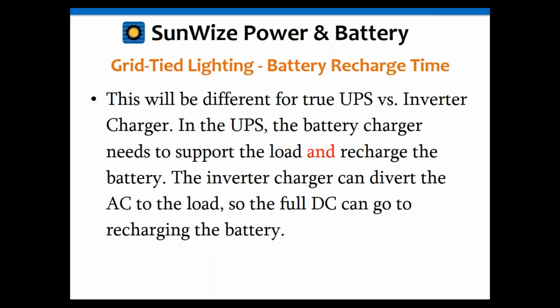Okay, now the recharge time. This is actually dependent upon whether you have a true UPS or inverter charger situation. The reason is for the UPS, the battery charger needs to support the load and recharge the battery at the same time. Remember, everything is going through the battery, so all power has to come off that battery and charger. Whereas with the inverter charger, because of that transfer switch, it can then divert the AC to the load, so then the full charge it has, the full DC current, can then go to recharging the battery.